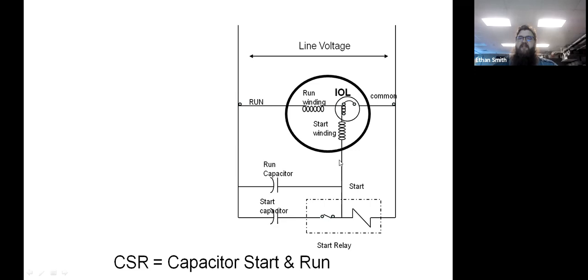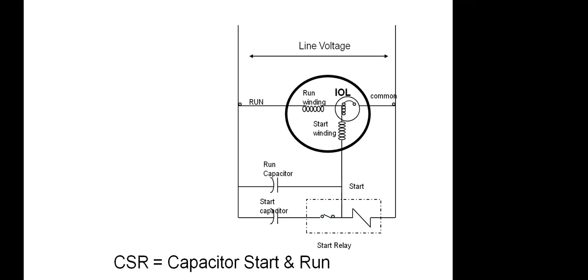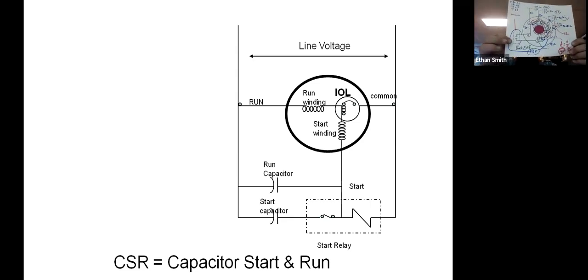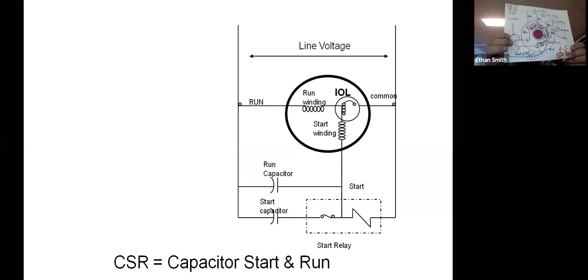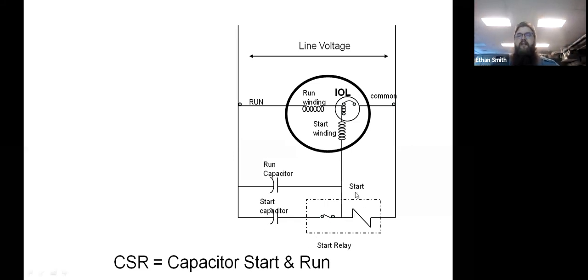Okay, so what happens in the start winding to the voltage when that motor is spinning? Anybody remember? It goes up. That start winding voltage is the same as our capacitor voltage. And so that start winding, when that is running, is getting a lot of back EMF. So your potential relay has a coil that's sized for, if you look at the voltage rating on a start relay, it's rated for the back EMF of your motor.